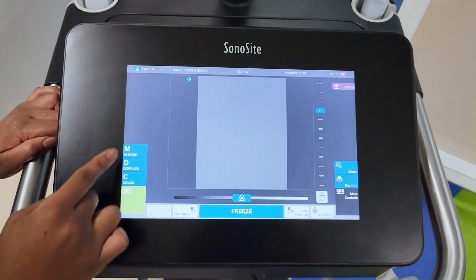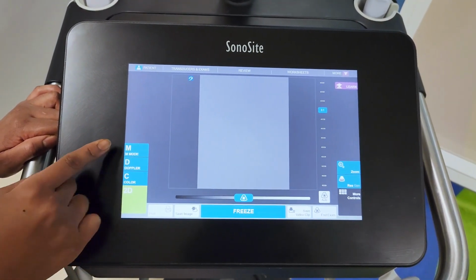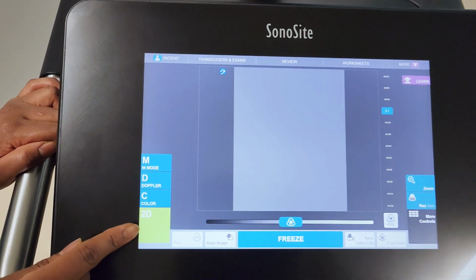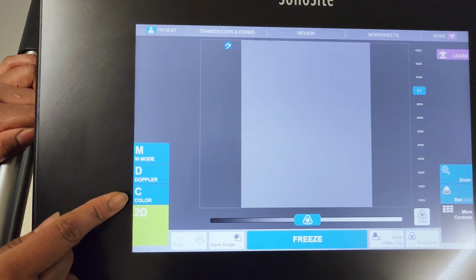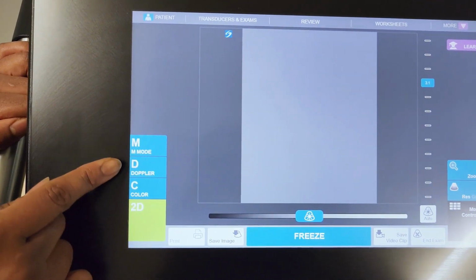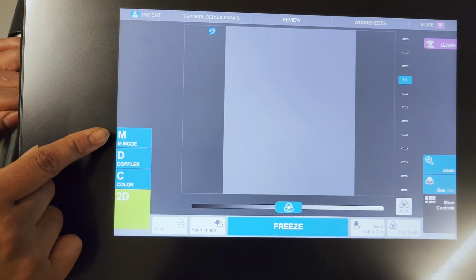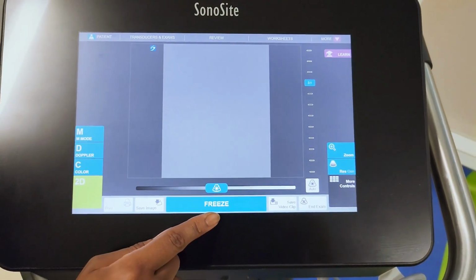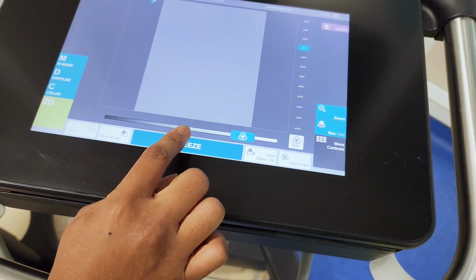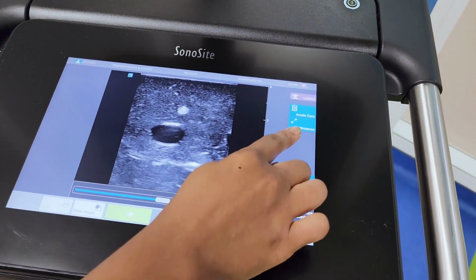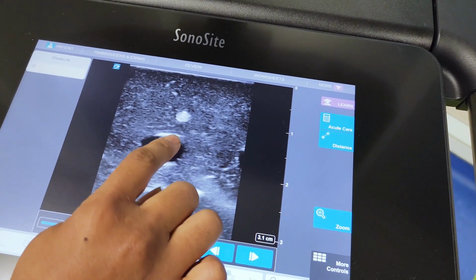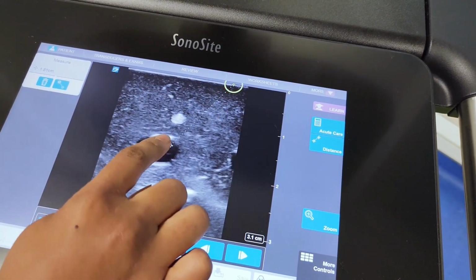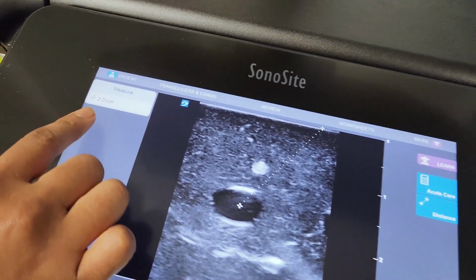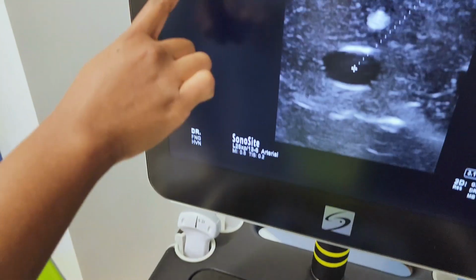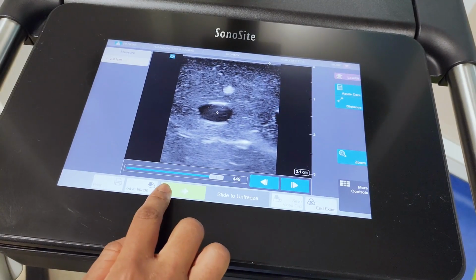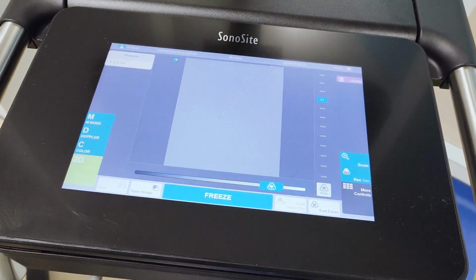The modes menu is shown on the left side of the control panel display. The modes are the basic 2-dimension mode or 2D, C mode or color mode, Doppler or D mode, and motion mode, presented here as M mode. To freeze an image, simply hit freeze to activate it. Also, some controls appear when the image is frozen. Distance measures the distance between two points. These measurements will appear on both the left side of the control panel and the display screen. Slide to unfreeze to go back to the home screen, or double tap with two fingers on the screen.